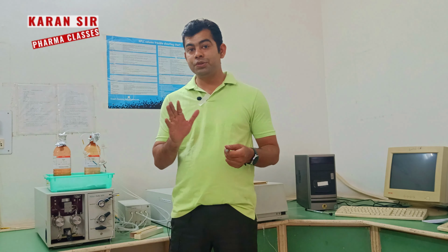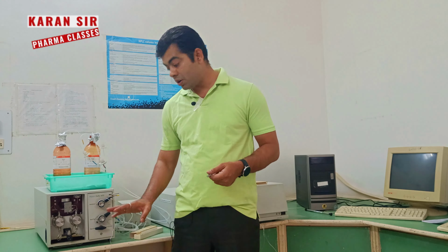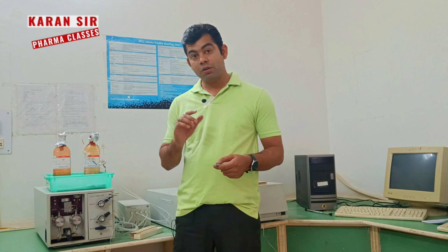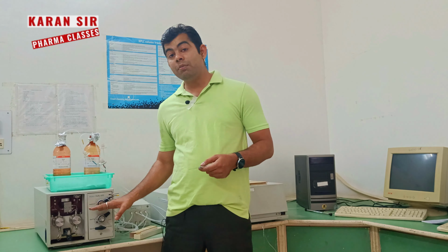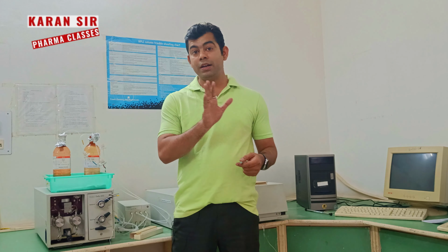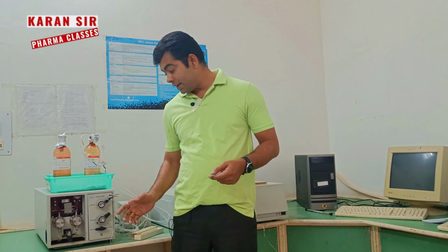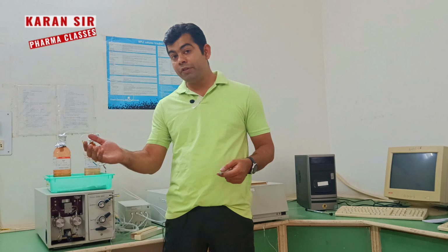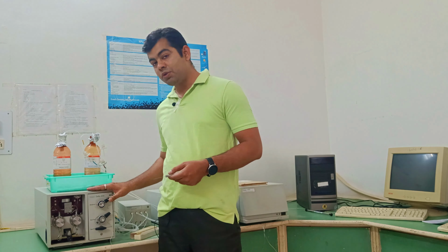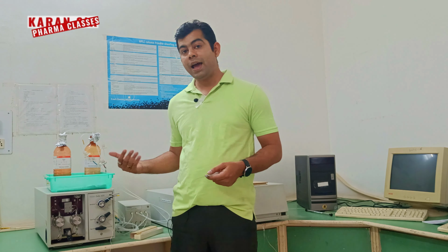Okay, so if anybody asks you what the analytical mode or semi-preparative mode is, tell them analytical mode is used for general purposes. We do not regenerate our sample again, but in semi-preparative mode we collect our sample again after analysis, that is, regenerate our sample. Right now this instrument is set in analytical mode.